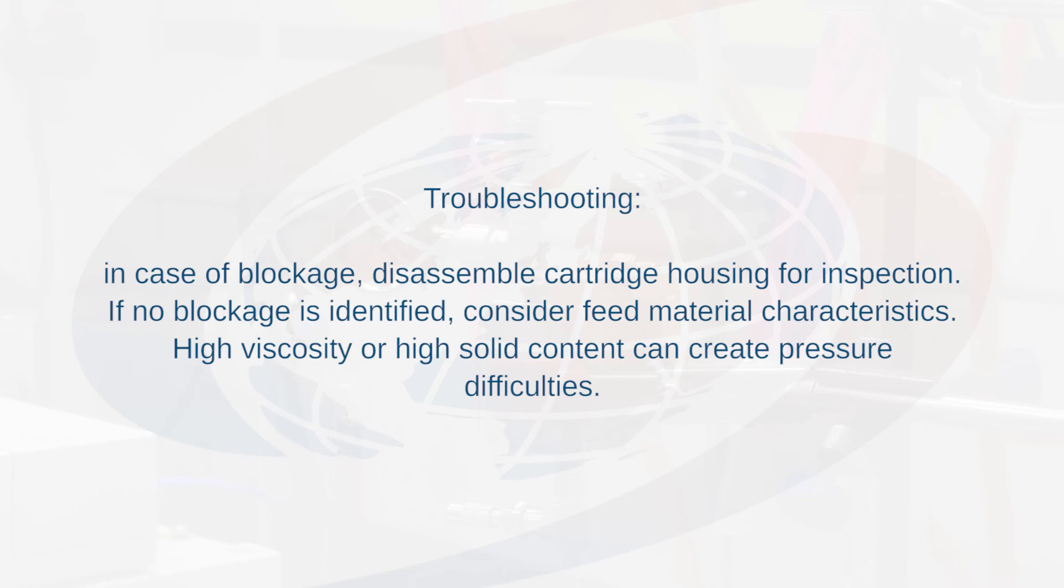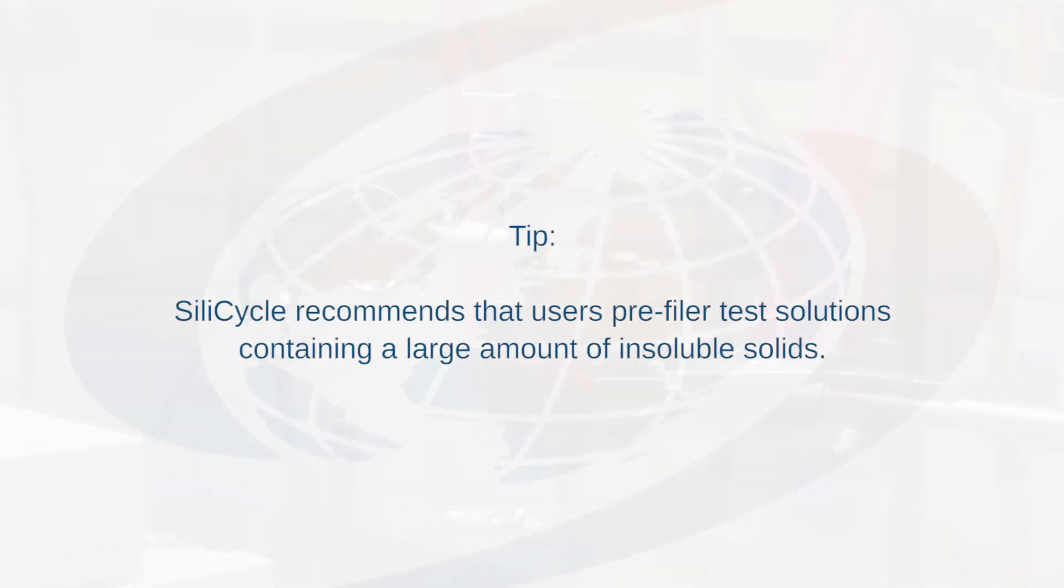If no blockage is identified, consider feed material characteristics. High viscosity or high solid content can create pressure difficulties. SiliCycle recommends that users pre-filter test solutions containing a large amount of insoluble solids.